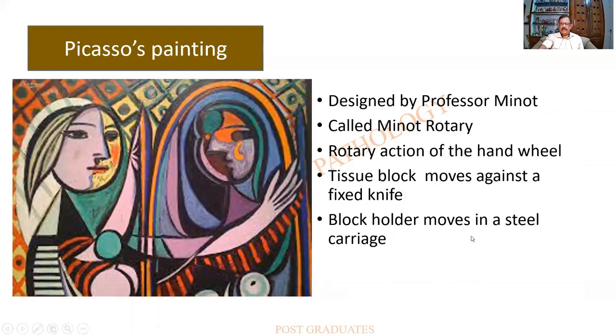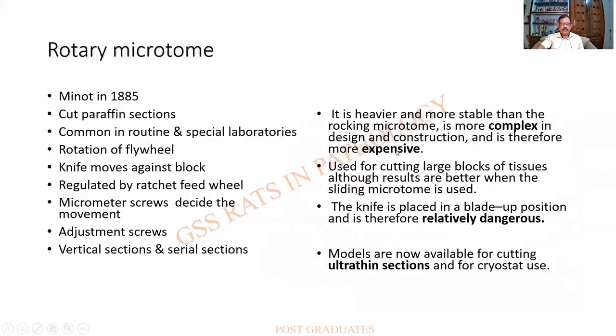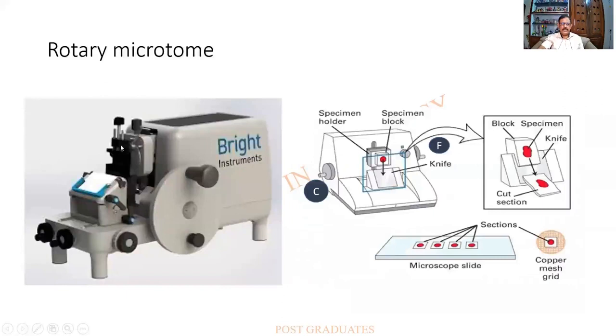Coming back to the rotary microtome — here is a much better modern version. There is a block holder which can be tightened by screws, and a knife whose angle can be adjusted. The instrument is quite heavy and sturdy, so vibrations are minimal. The fine adjustment is set for a certain number of microns, and with each complete rotation it advances the block by that many microns.